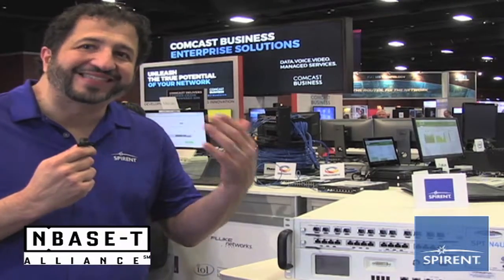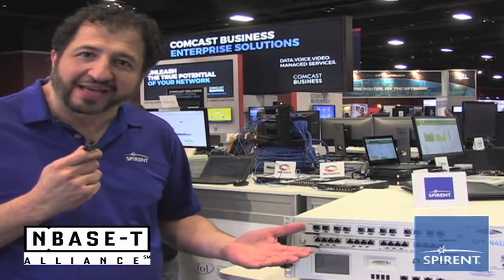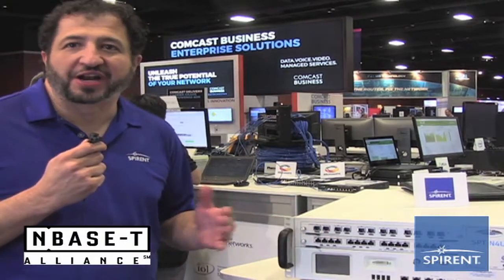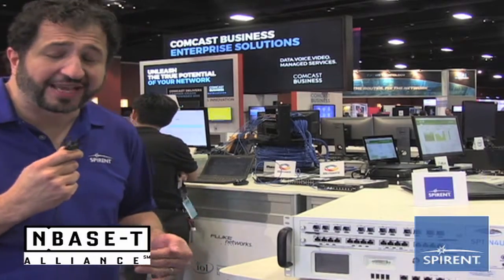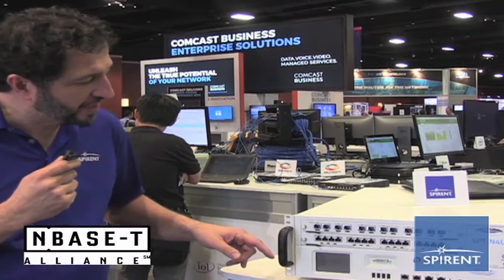It'll do all the handshaking, plus it'll do various load conditions to test the behavior of the PSE in extreme wattage scenarios and shorts and opens, just to see how the behavior acts in that type of environment.